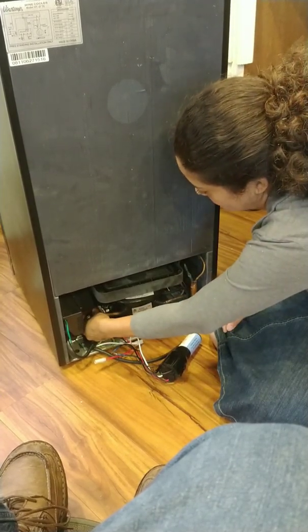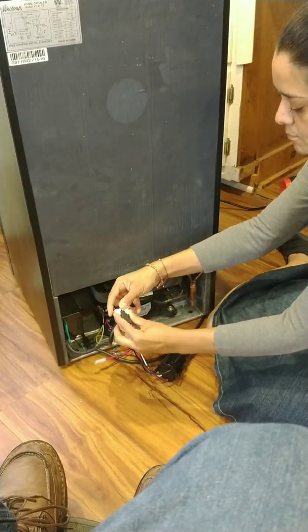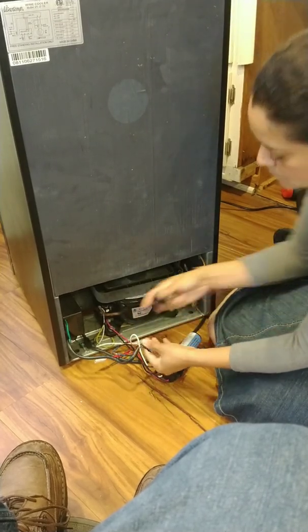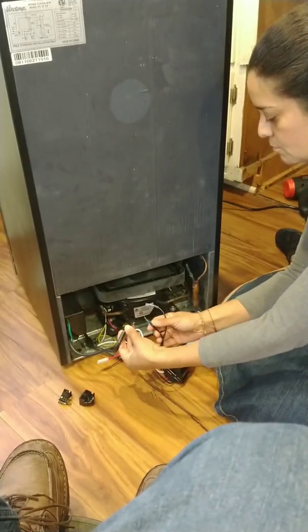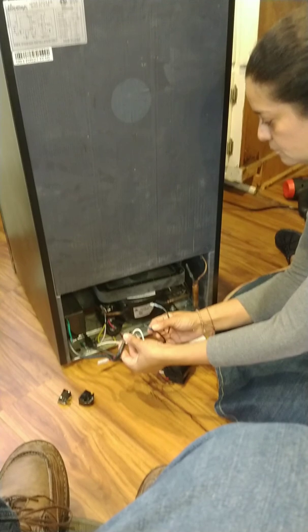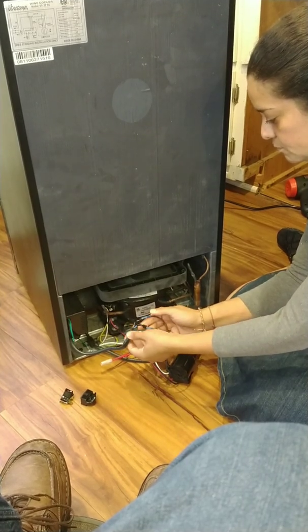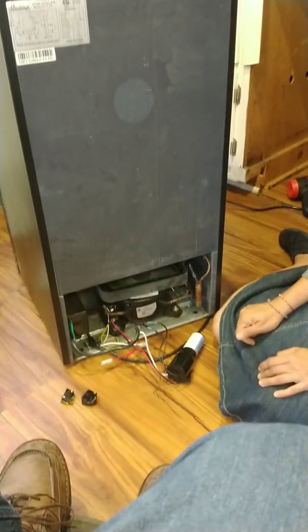We've already disconnected it. We'll pull it out and show you — they all come with some sort of relay and a safety heat switch. There are two wires connecting to it, essentially the power going into the compressor. We set those aside. Usually one of those has gone bad. We tested with a voltmeter — there are videos on YouTube for testing the compressor to make sure it's good. As long as all three windings inside have good resistance against each other and none are grounded, the compressor is working.